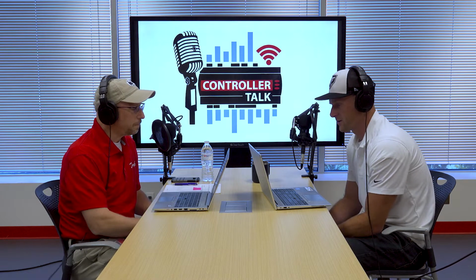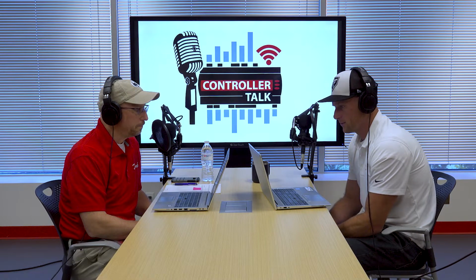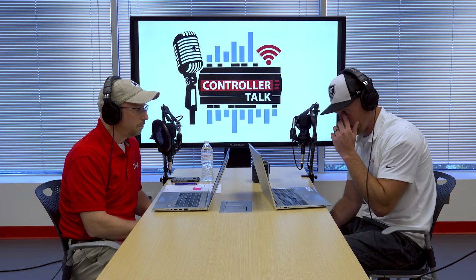So if we're looking at heat reclaim first in the system managers, option 1 is just narrowed in on the HVAC controller. In your HVAC system manager, you have your rooftop units or air handler set up. And you get questions right in there for heat reclaim and how many stages you have, and you can assign your relays and your set points and all that good stuff. Yep. We know we're controlling the 3-way valve, and that's all happening right there in that controller. End of story. Nothing else involved. Nothing on the refrigeration side. Nothing on the rack side. That's right. So pretty straightforward, pretty simple, especially in terms of the other 2 options. So that's where you start if you want something at the bare minimum.